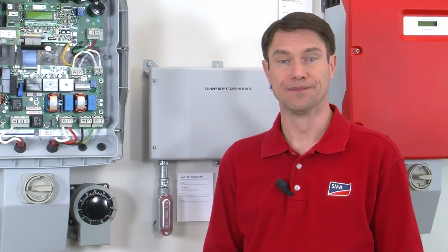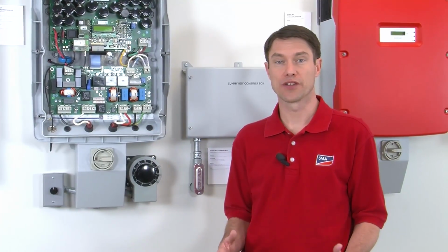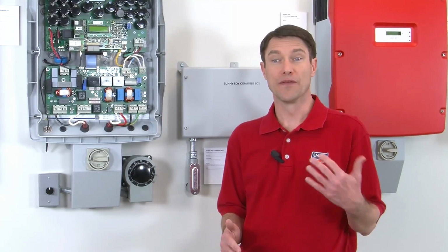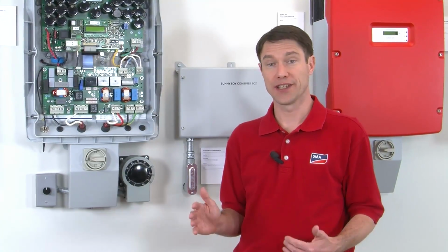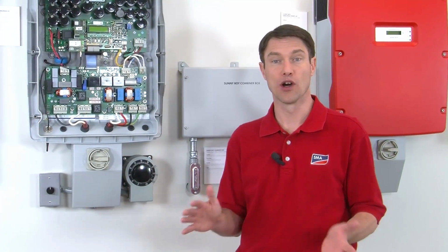Now for US series inverters, everything is synced for a 60 Hertz grid. So 60 Hertz or 60 cycles per second is the nominal or perfect value for frequency. And while the perfect value is 60 Hertz, the inverter will operate normally from 59.3 all the way up to 60.5 Hertz. That's its acceptable window of operation.